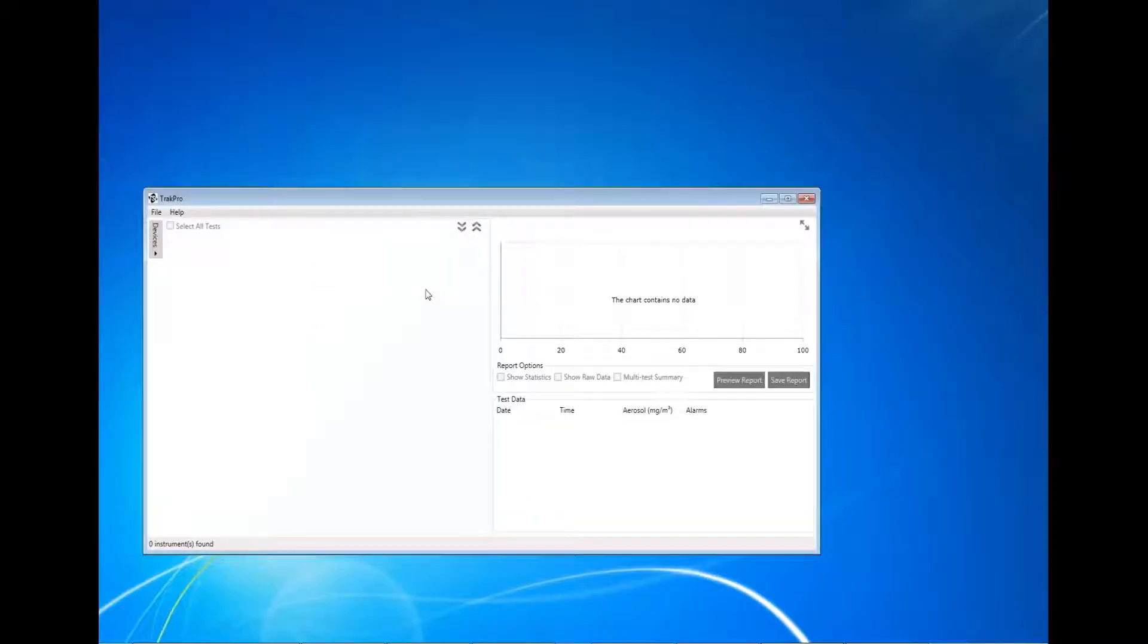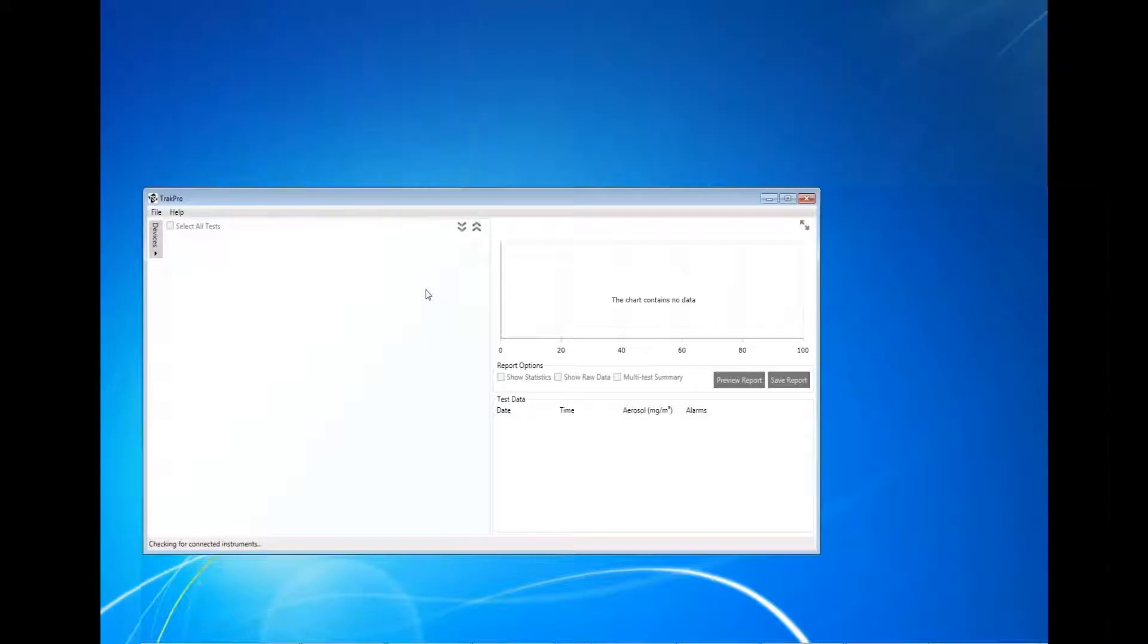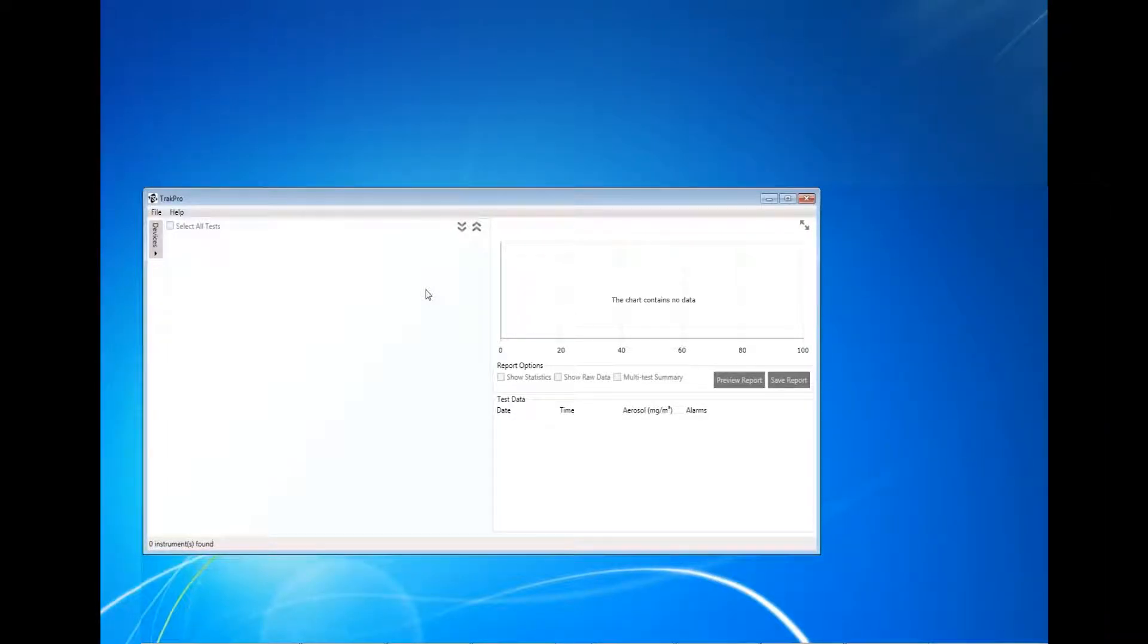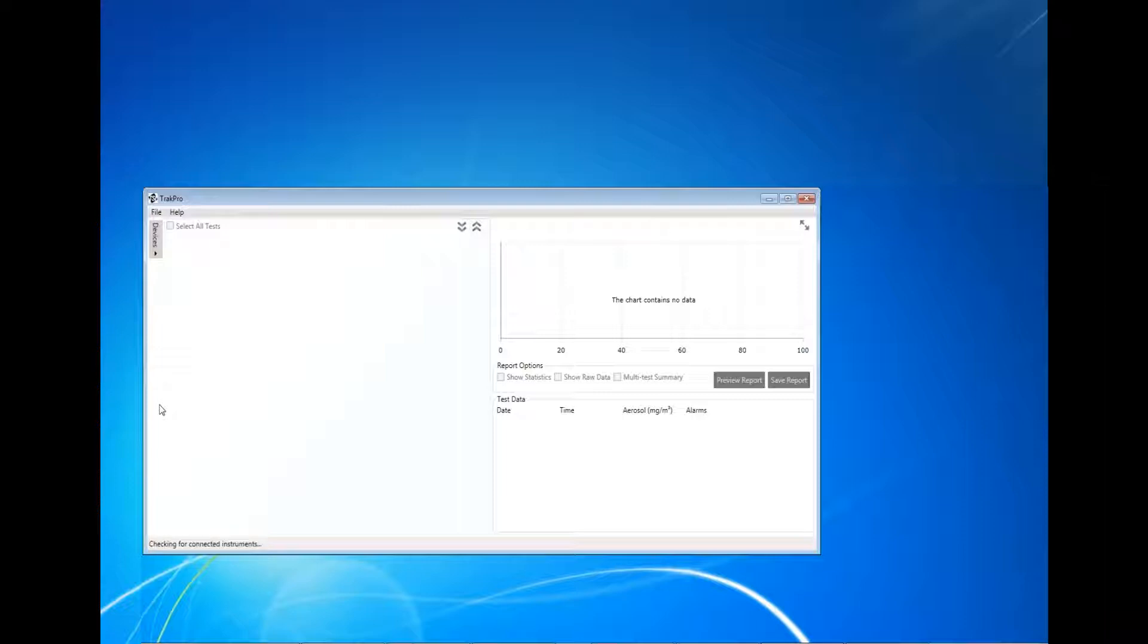After TrakPro 5 has been installed onto your computer, you can use it to download log data from the instrument. To do this, you will need to connect it to your computer. This can be done using the USB cable that was provided with the instrument. It is important to note that when downloading log data, the instrument must be powered on.